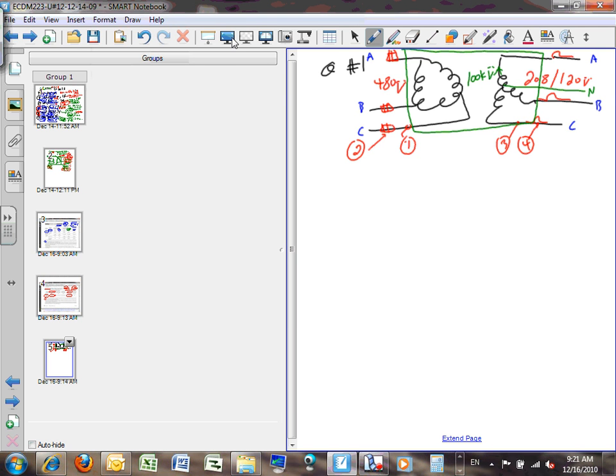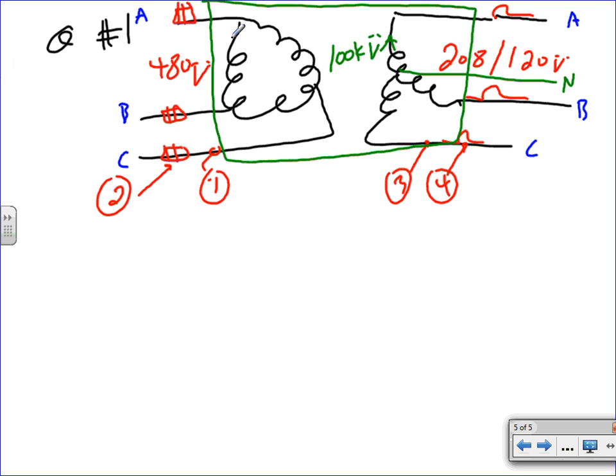I used for receptacles. A typical transformer used for receptacles. Okay, delta-Y, 208/120. We need to size the fuses and the circuit breakers, both on the primary and the secondary and the feeder. The primary and the secondary and the feeder.